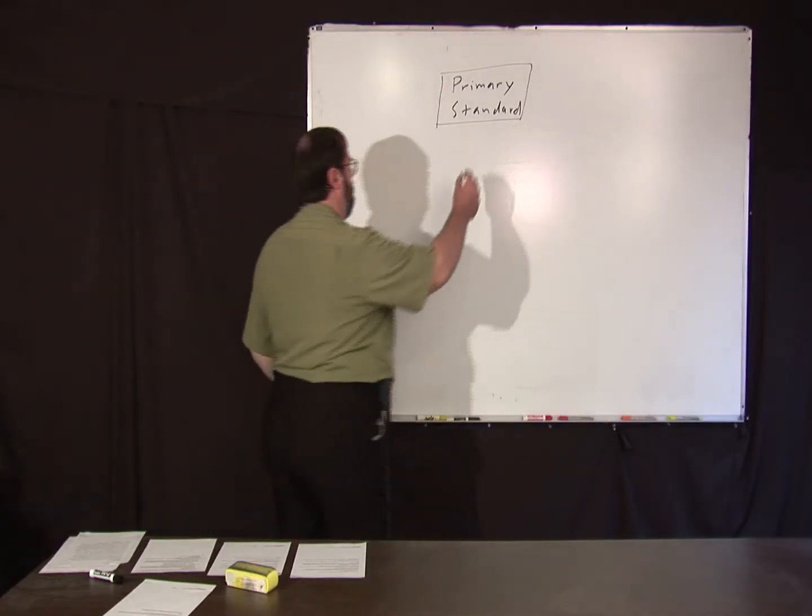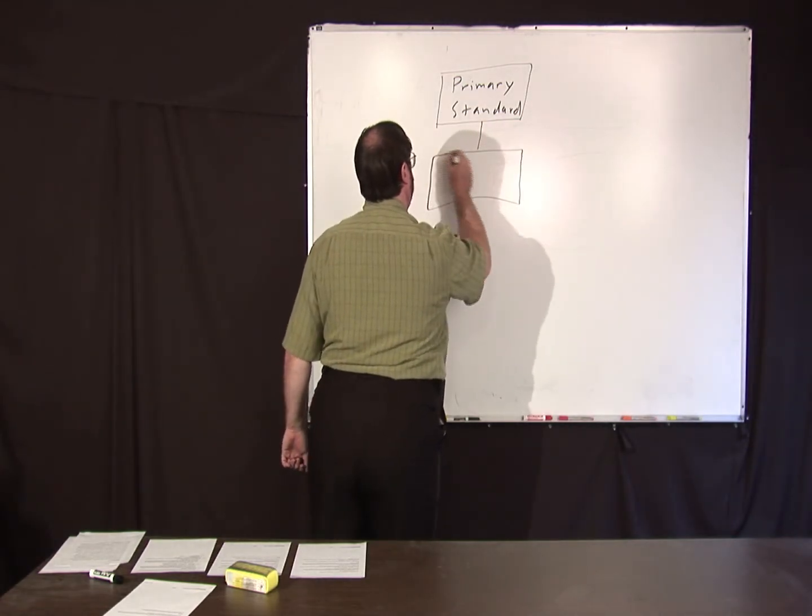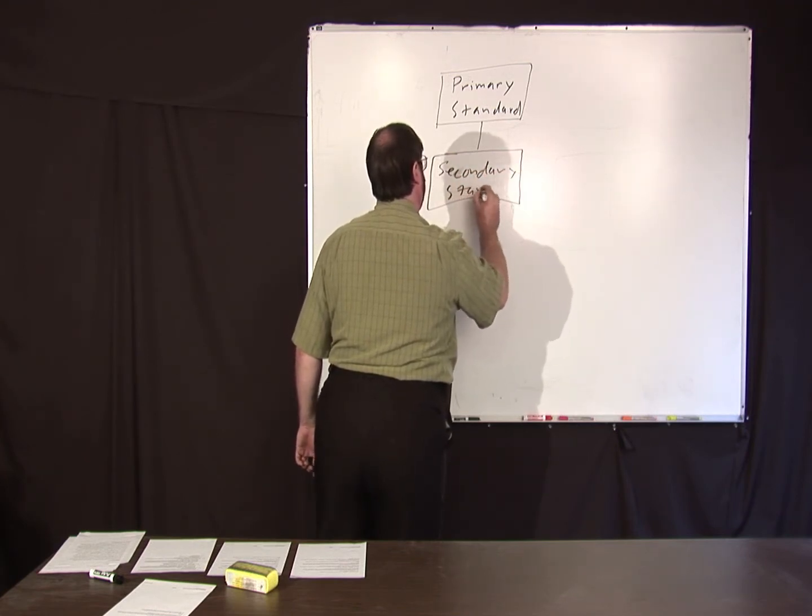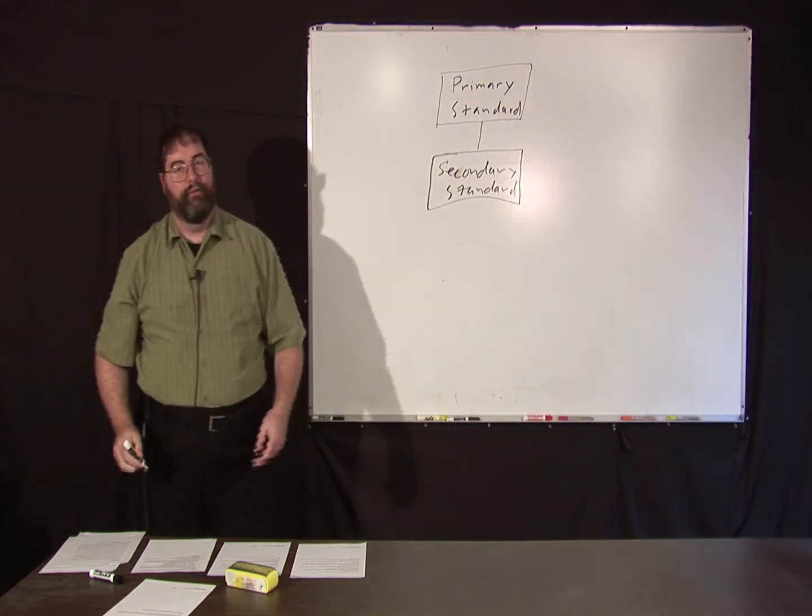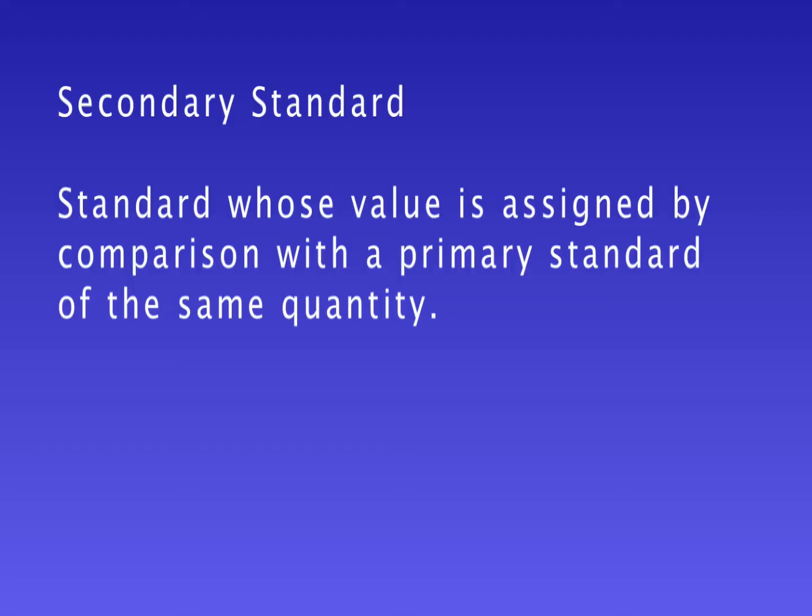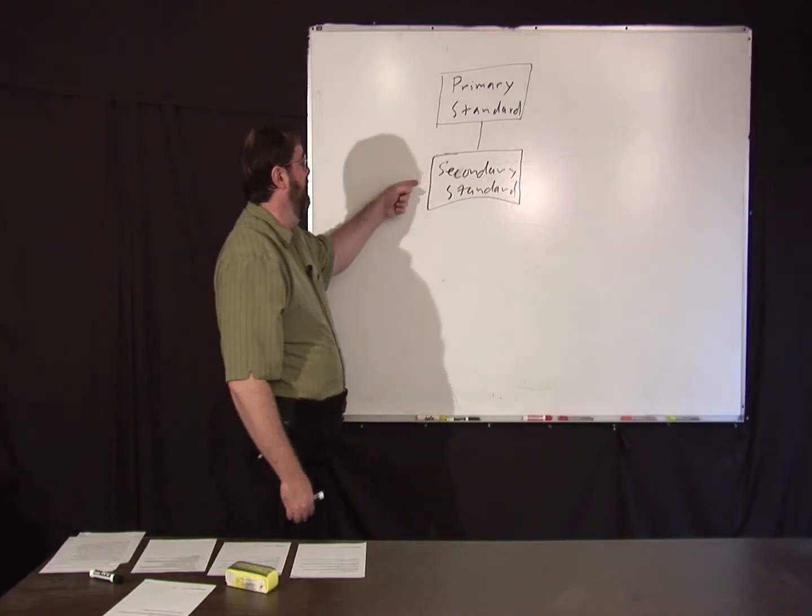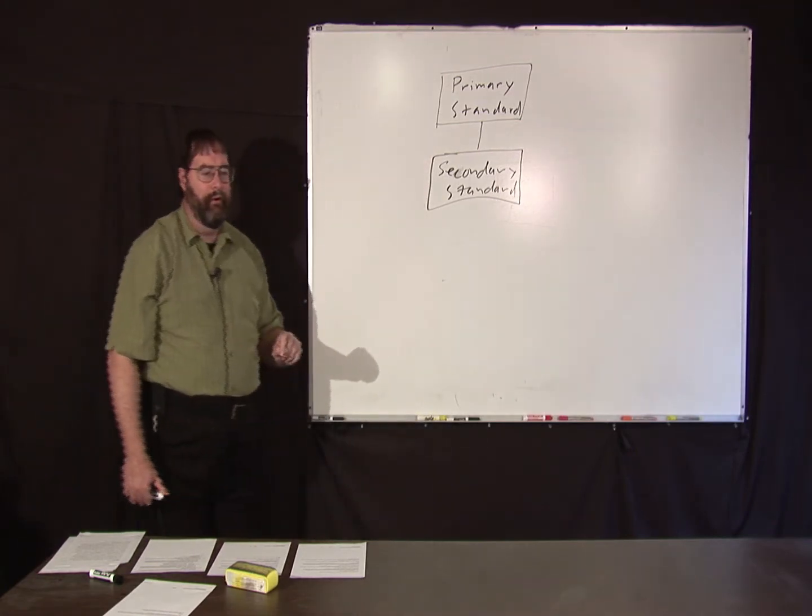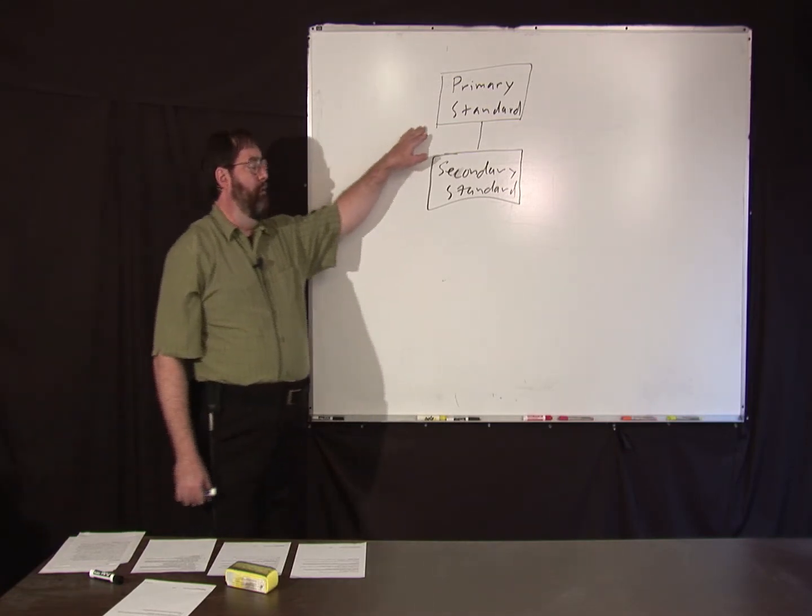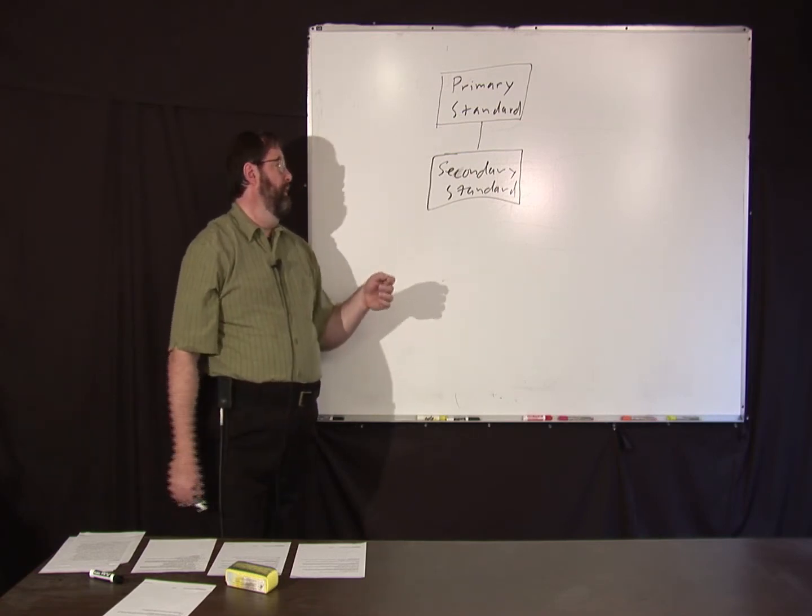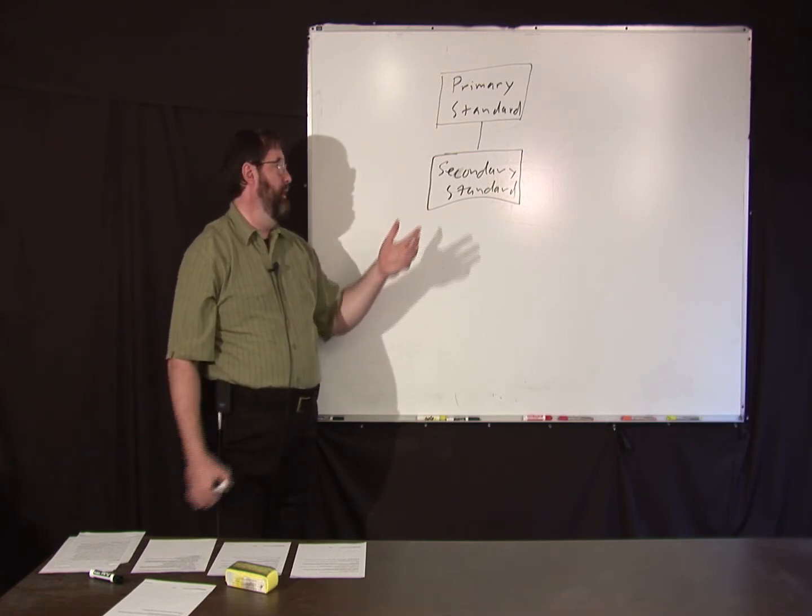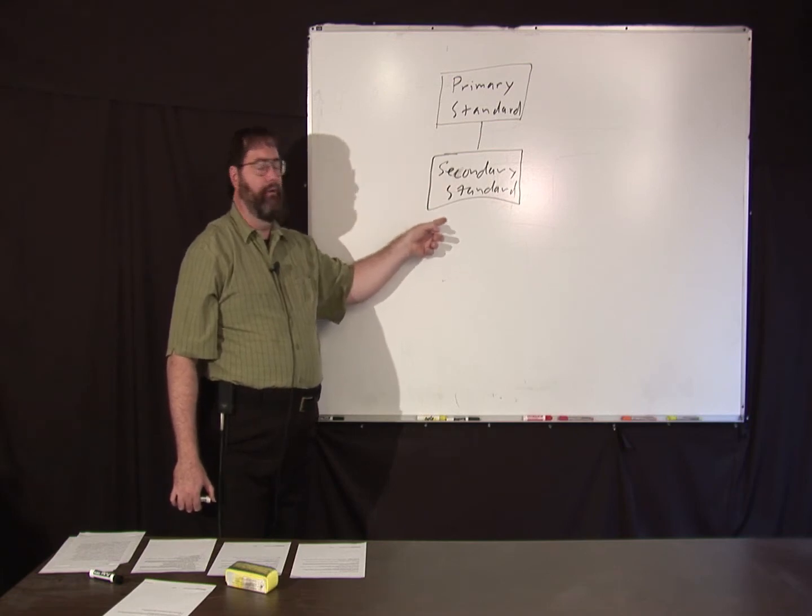From that, you can calibrate secondary standards. A secondary standard is defined by the VIM as a standard whose value is assigned by comparison with a primary standard of the same quantity. So, you might be comparing a solid-state voltage reference somehow to a Josephson Junction voltage standard, for example, or somehow you've got a primary standard definition of the meter and you're comparing it against that, or possibly a triple-point cell compared to some sort of reference thermometer.